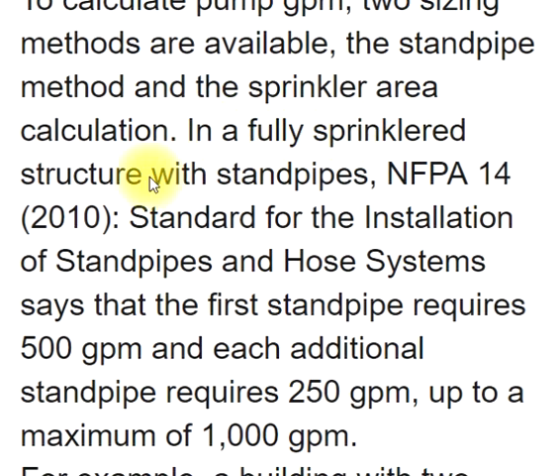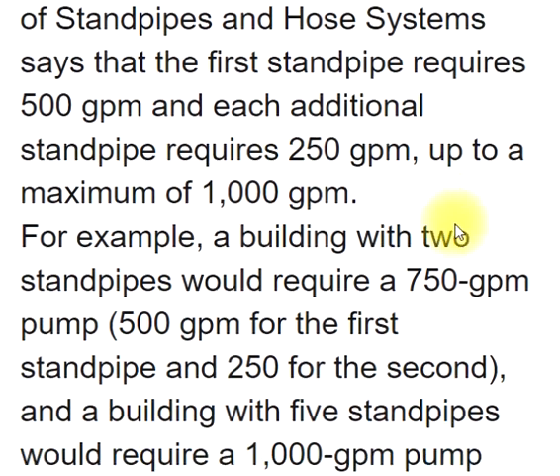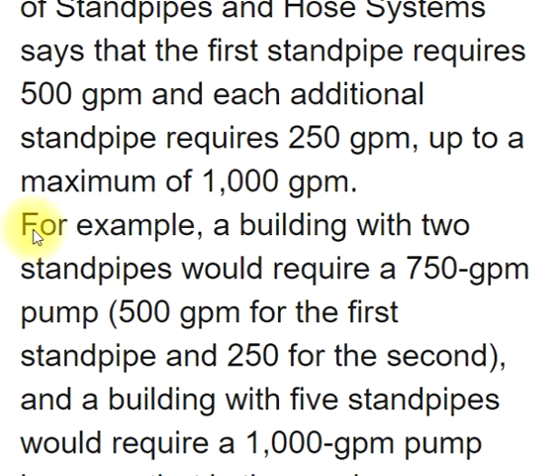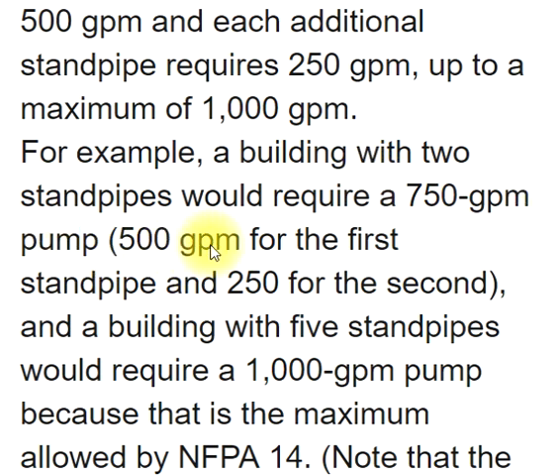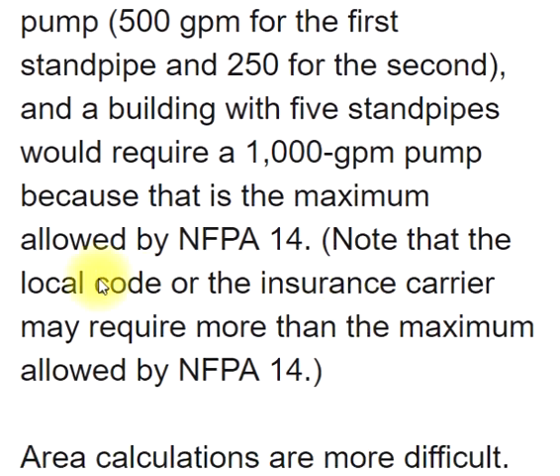In a fully sprinklered structure with standpipes, NFPA 14 (2010 standard for the installation of standpipes and hose systems) states that the first standpipe requires 500 GPM and each additional standpipe requires 250 GPM, up to a maximum of 1,000 GPM. For example, a building with two standpipes would require a 750 GPM pump (500 GPM for the first standpipe and 250 for the second), while a building with five standpipes would require a 1,000 GPM pump — the maximum allowed by NFPA 14. Note that the local code or insurance carrier may require more than this maximum.